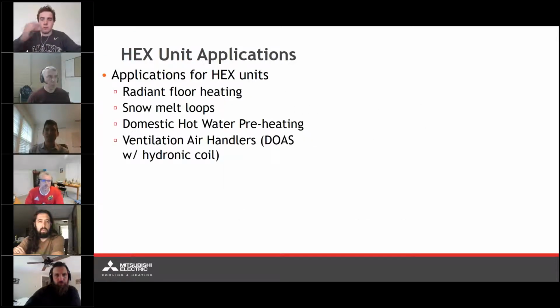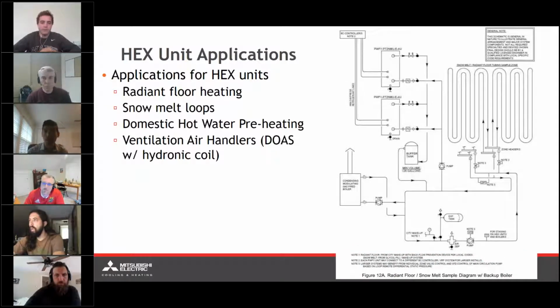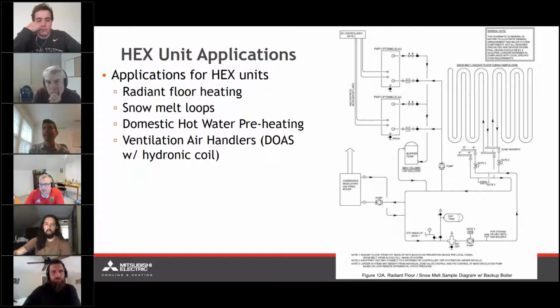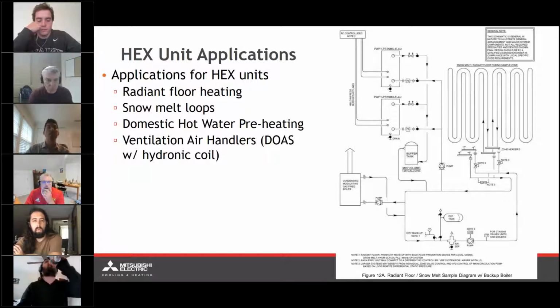All right, in terms of potential applications for a HEX system, right off the bat, one potential application is a radiant floor heating loop or a snow melt loop, something that could be popular in the Northeast. Now, the water temperatures in the HEX are capable of being heated within the range of supplemental heat for in-floor radiant heating, as well as snow melt loops. Now, we should consider whether or not this will be done in tandem with an existing or a third-party fossil fuel-driven boiler, or it could potentially be done without it and be entirely electric-driven.